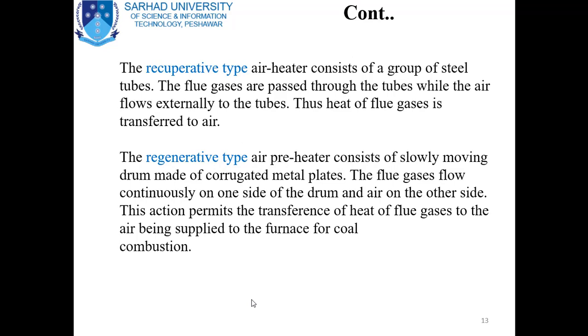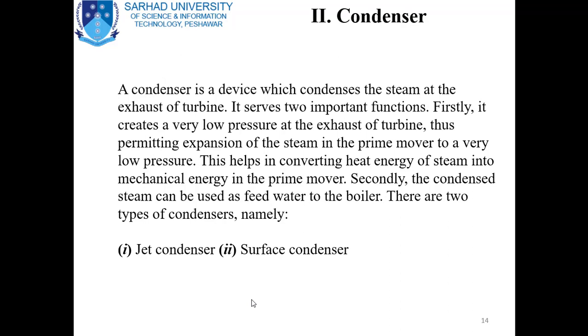Number two constituent is the condenser. A condenser is a device which condenses the steam at the exhaust of the turbine. It serves two important functions: firstly, it creates a very low pressure at the exhaust of the turbine, thus permitting expansion of steam in the prime mover to a very low pressure, which helps in converting the heat energy of steam into mechanical energy.